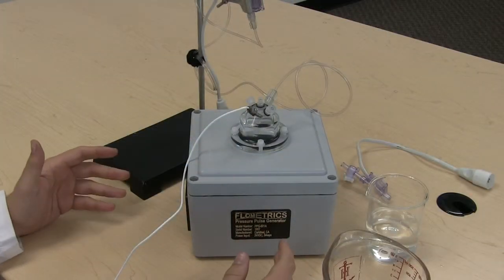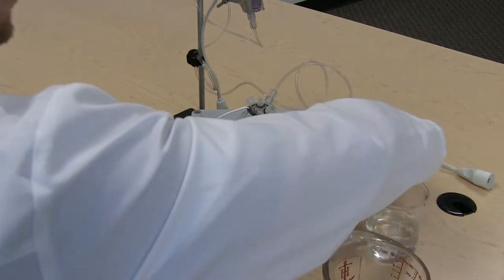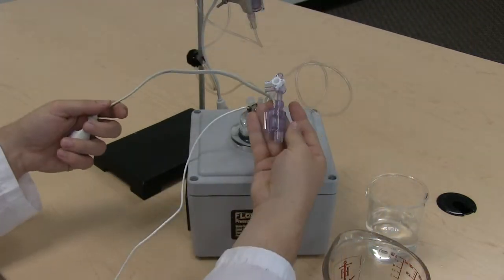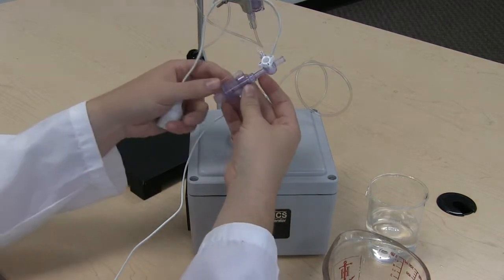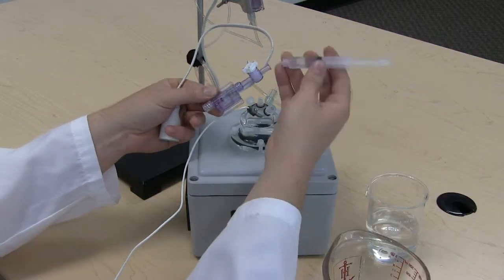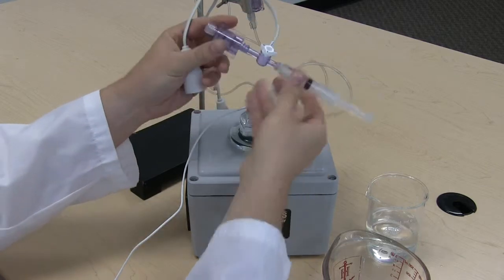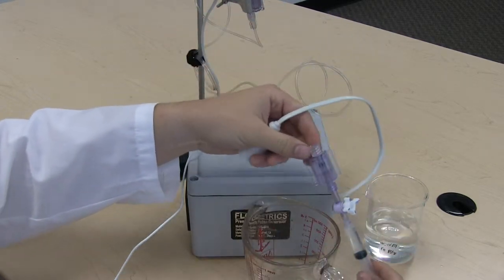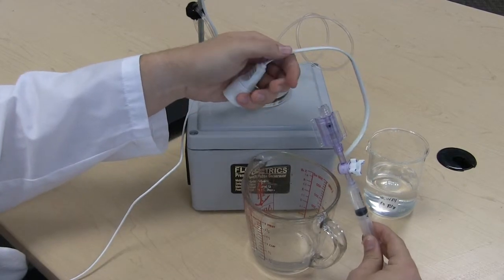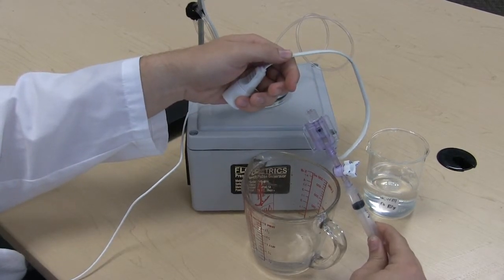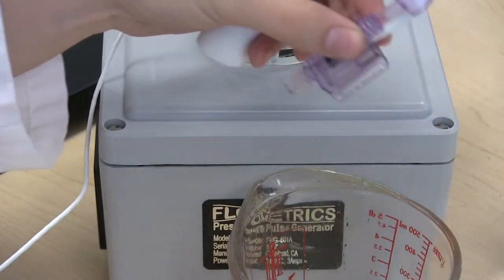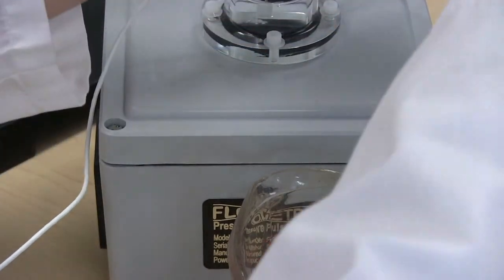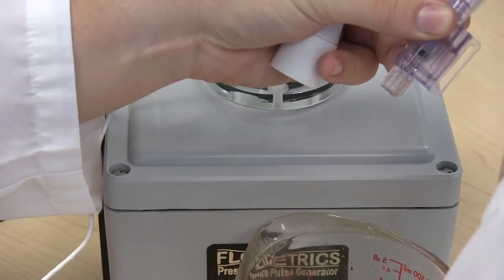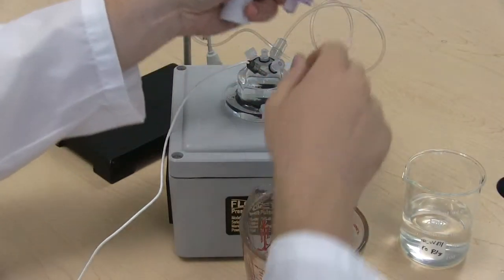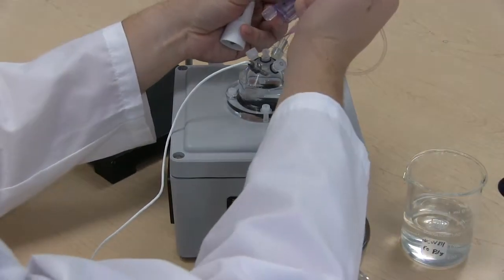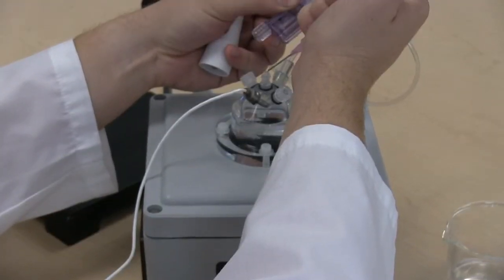Finally, we're going to connect a disposable pressure transducer to the PPG. Now, just like the catheter, the disposable pressure transducer has to be filled with water. One easy way to do this is with a syringe. We'll force water through the disposable pressure transducer and ensure that there are no air bubbles. We're going to push just a little bit more out to ensure that we have a tiny bead of water at the end, and we'll ensure that there's a bead in the fitting to which we will connect it.